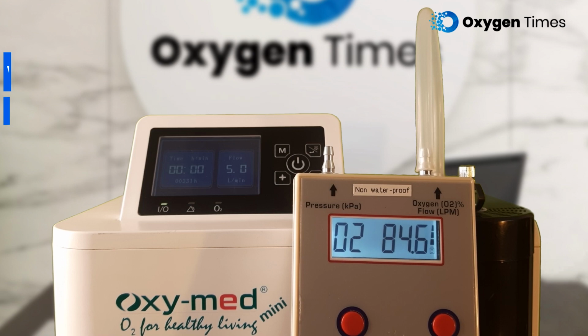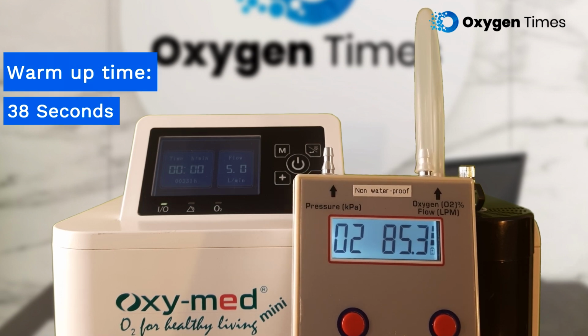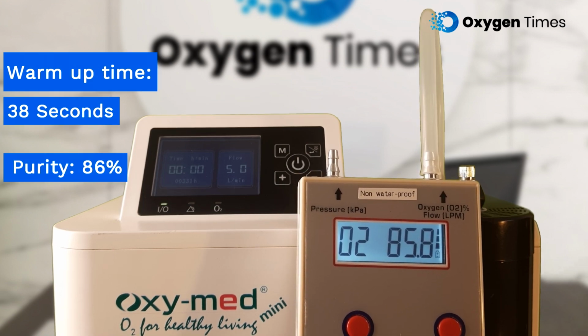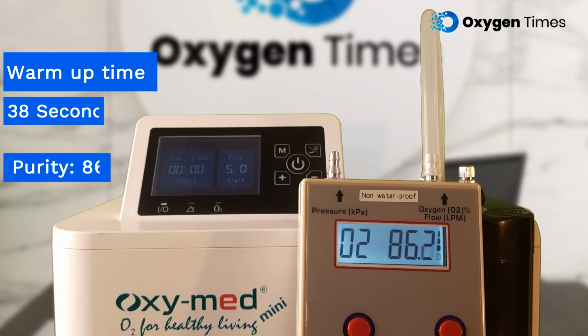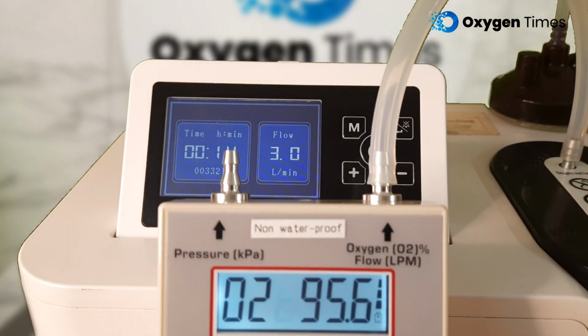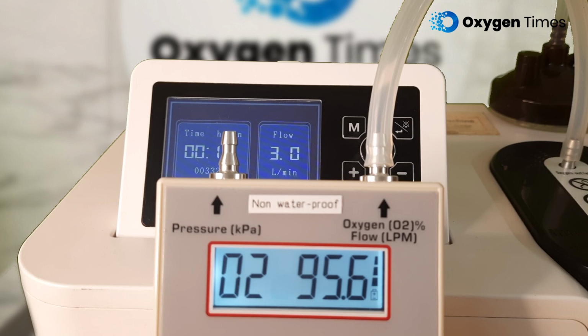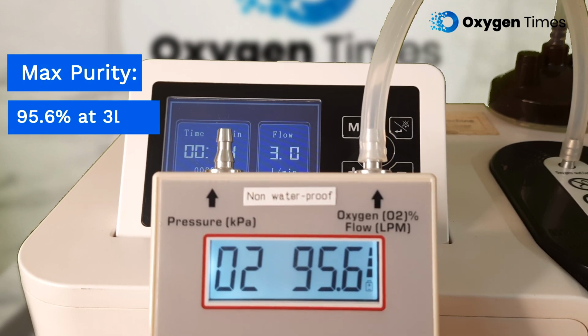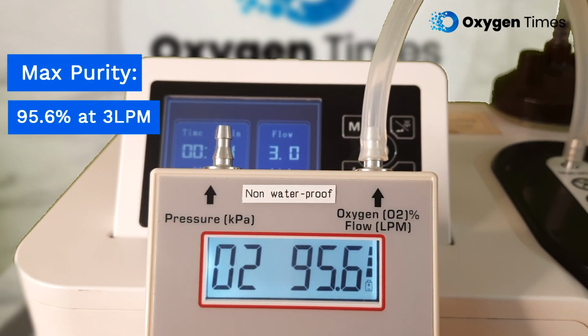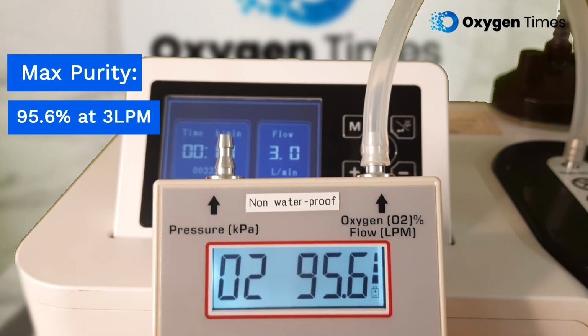In our warm-up test, we found that the Oxymed Mini took 38 seconds to deliver oxygen at a purity of 86%, one of the fastest in the industry. In total, it took 2 minutes and 25 seconds to reach its maximum purity level of 95.6% at a flow rate of 3 liters per minute.